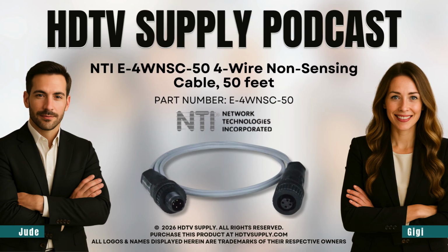But between them, you have, let's say, a 50-foot concrete hallway. No pipes, no water sources at all. It's a safe zone. So you wouldn't want to run expensive water-sensing cable across a totally dry hallway where you know a leak is impossible. Exactly. That sensing cable is pricey per foot. You don't want to waste it where there's zero risk. So you use the E-4WNSC-50. It just bridges the gap. It connects the sensors in one room to the sensors in the other, but it does it efficiently. It's like a highway connecting two cities. You don't need exit ramps in the middle of a desert.